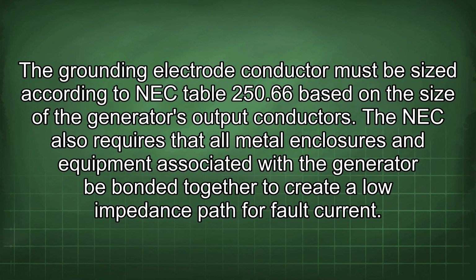The grounding electrode conductor must be sized according to NEC table 250.66 based on the size of the generator's output conductors. The NEC also requires that all metal enclosures and equipment associated with the generator be bonded together to create a low impedance path for fault current.